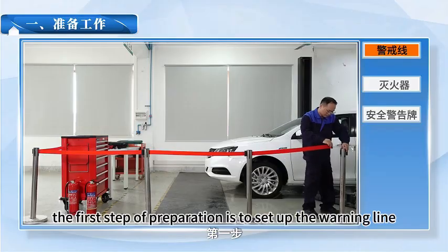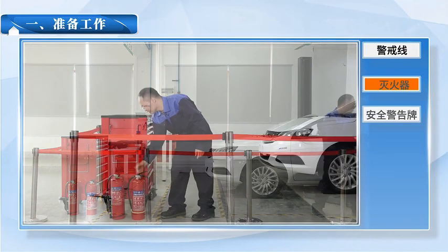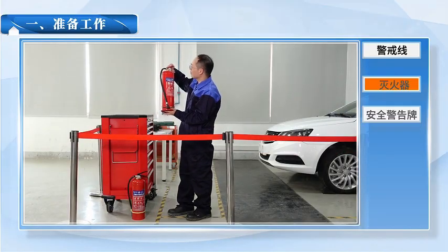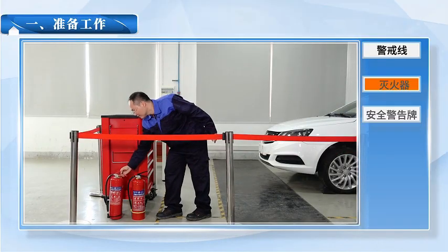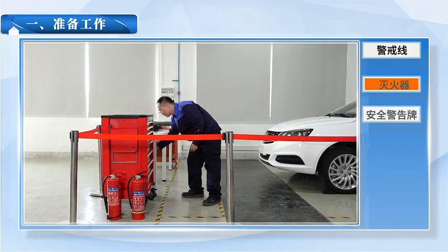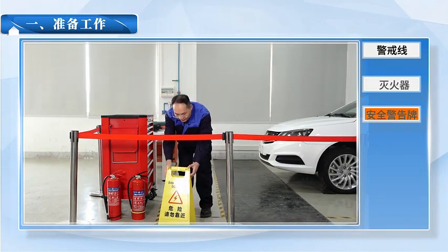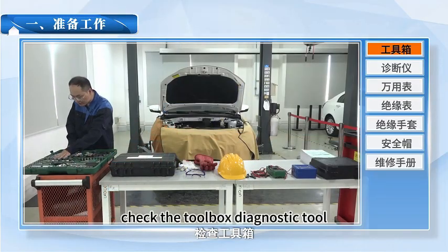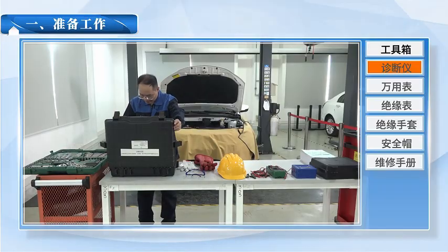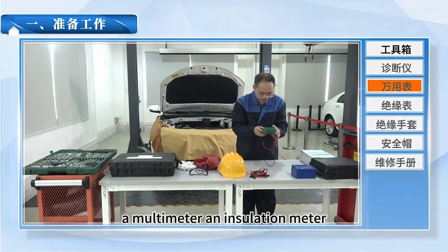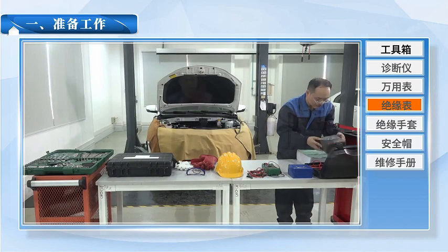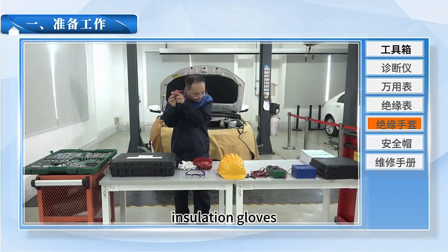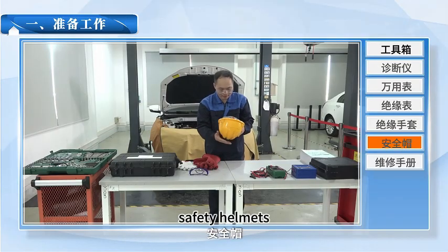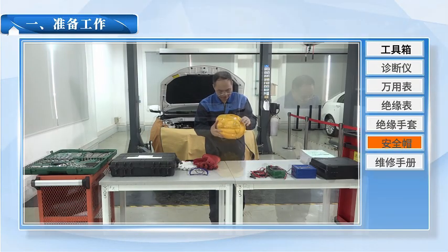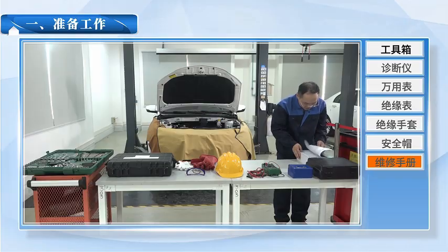The first step of preparation is to set up the warning line. Check the fire extinguisher. Place a safety warning sign. Check the toolbox, diagnostic tool, a multimeter, an insulation meter, insulation gloves, safety helmets, maintenance manual.